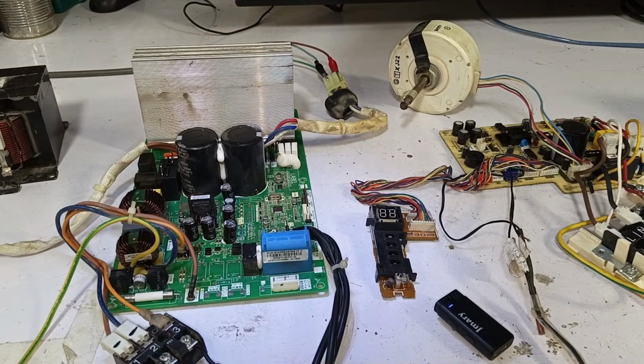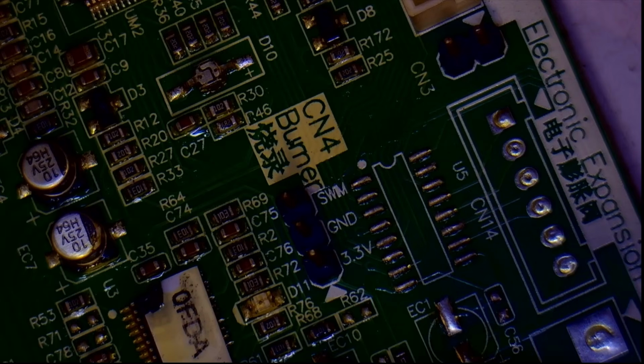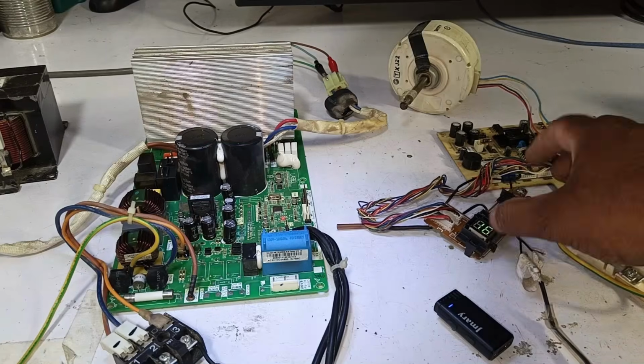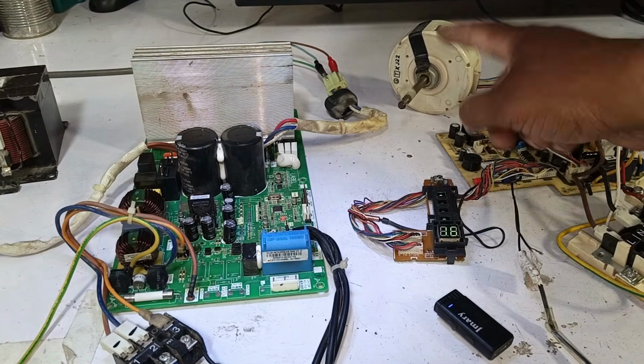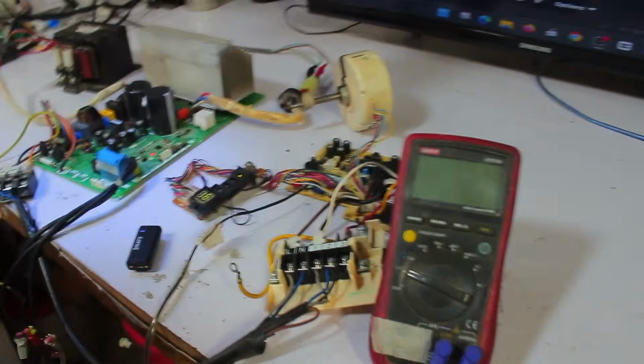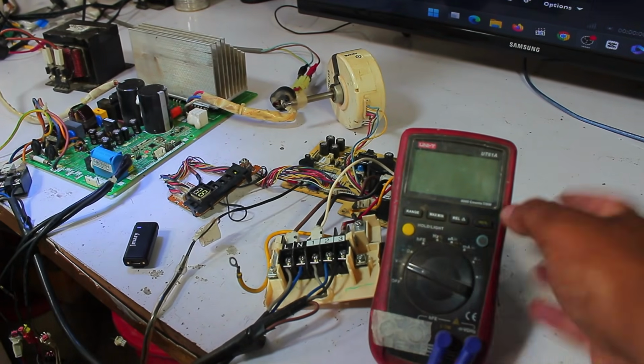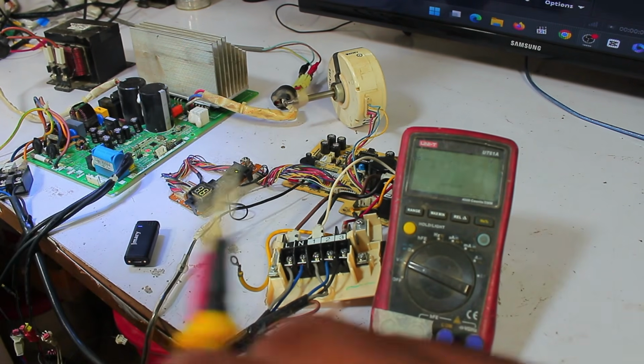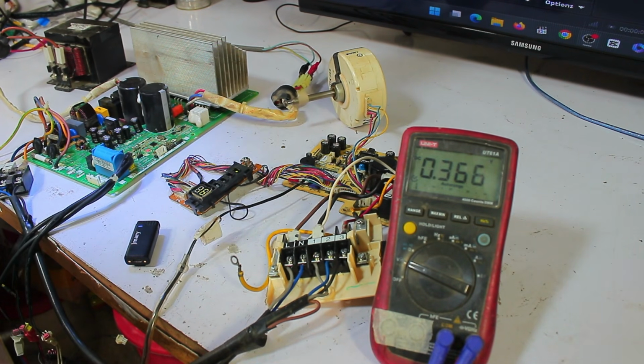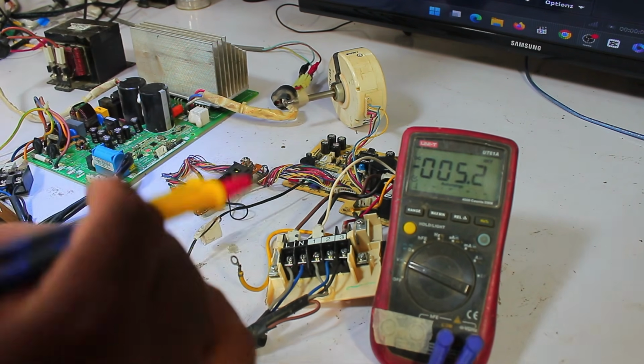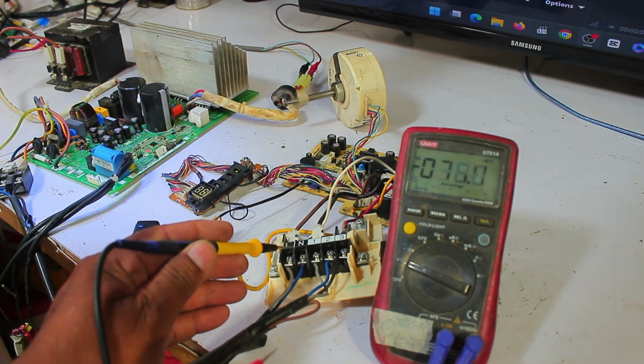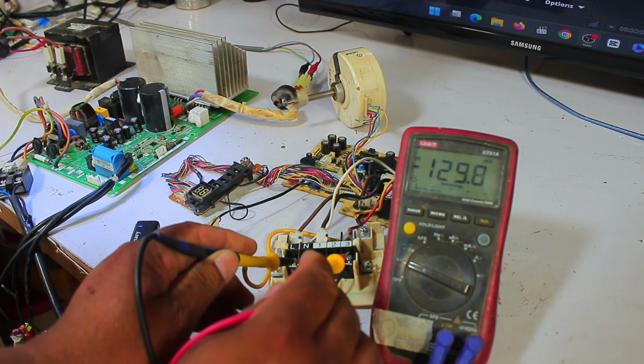Now I have given power to the indoor unit, and the outdoor unit has turned on. Look, it's working at 16 degrees. The indoor fan motor has also started running. Since this PCB was showing an H11 error, we will quickly check whether the H11 error is still present in it or not. It does not seem like the error is still there. It looks like it has been fixed. But still, we will confirm it properly.